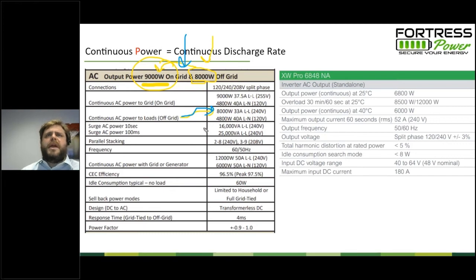But what I really wanted to point out with continuous output power is that there are some other spec sheet items on inverter sheets that might lead you to think the inverter is capable of outputting more than its rated power. So we're really talking about an 8 or 9 kilowatt inverter here, but it says, oh look, it could surge up to 16 kilowatts for 10 seconds, or it can surge to even 25 kilowatts for a tenth of a second. Sometimes these features are called surge ratings or burst mode ratings.